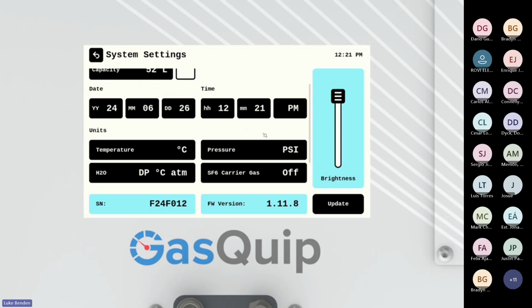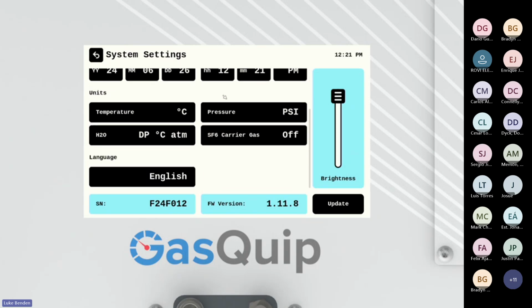Date and time, and then we have units. So temperature, pressure, the H2O units here we can change to ppmv if we'd rather have that, which a lot of people do. SF6 carrier gas, this is a way for you to test mixed gas breakers, especially in a lot of cold environments. They have mixed gas breakers that have CF4 inside of the breakers.